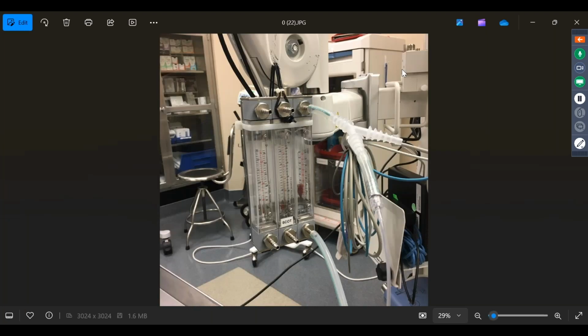Again, I use glass flow tubes to do all my flow checks and calibrations. Two important things. You jack the nitrous all the way up, and then you crack the O2 open, and you want to see the O2 go up without the nitrous moving until it hits like 200 cc's, and then you'll see the nitrous come on. That's to prevent delivering a hypoxic mixture. You want to have like 200 cc's of oxygen to support life. And it functions at a ratio.